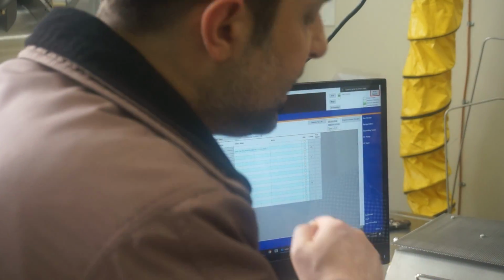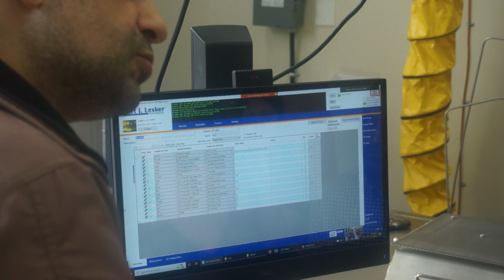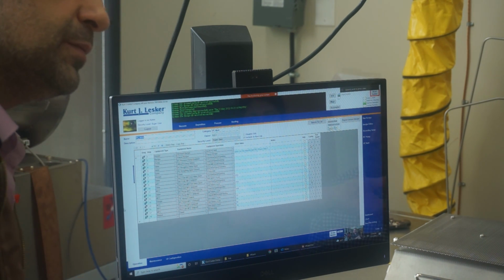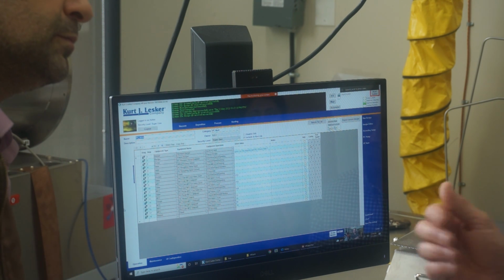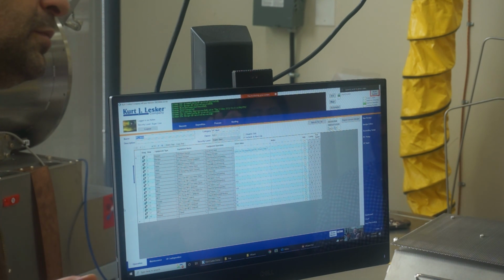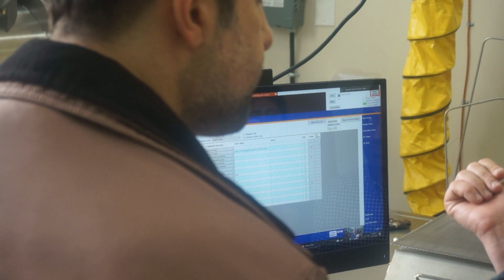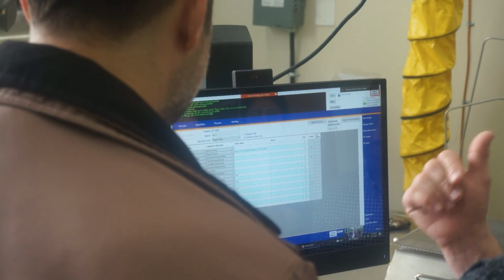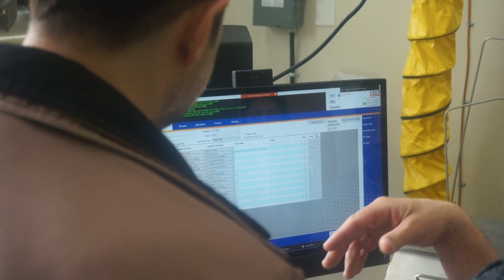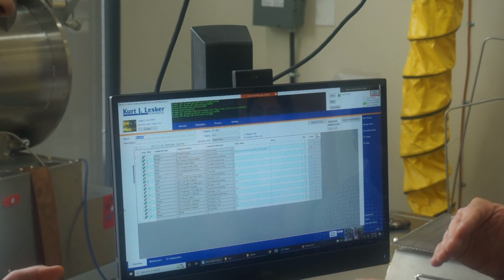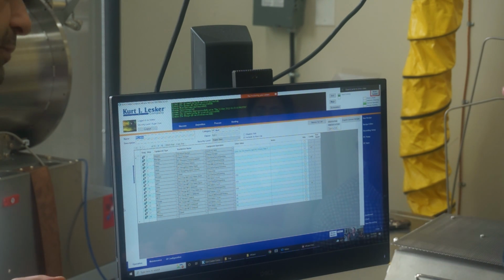I'm a little bit confused about PC vent and PC pump. What is this one? Vent allows you to retrieve the sample. Pump puts it back under vacuum. So one brings it to atmosphere, the other one pulls it back to vacuum. We'll cover PC pump, PC vent, and the processor. I don't have to go through every recipe, because once you understand the steps of those, you can understand the rest of the recipe.